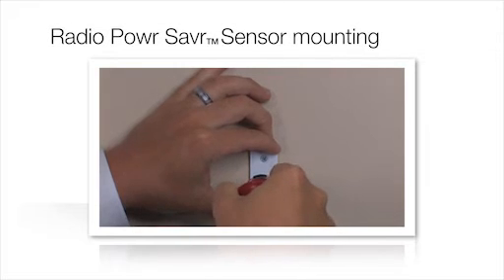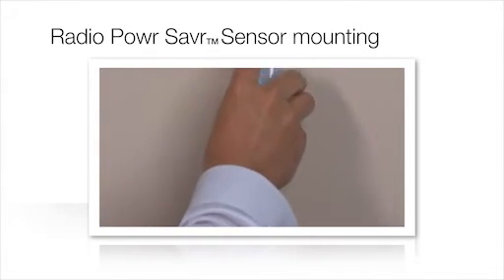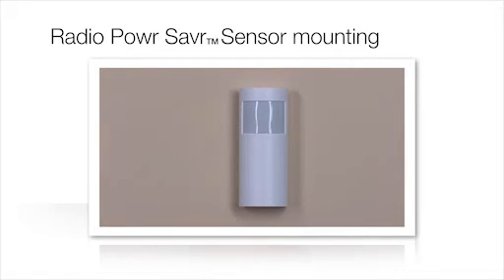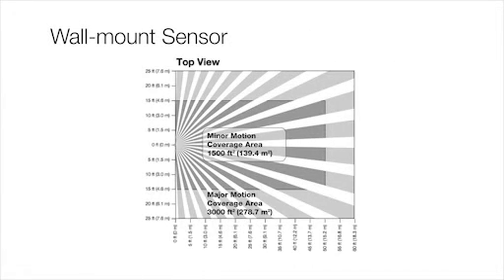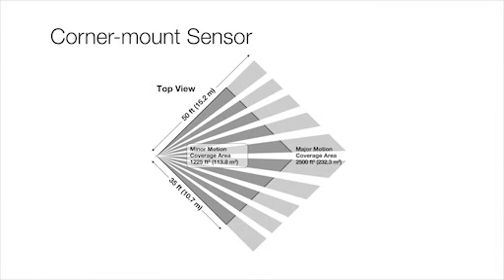Sensors can be mounted temporarily to verify placement and coverage, and then mounted to a wall or ceiling. Use up to six occupancy sensors in one space to achieve maximum coverage. The number of sensors required will depend upon the room size. Please refer to the Detection Range for Fine Motion chart in the Specification Submittal online for Radio Powr Savr occupancy or vacancy sensors.